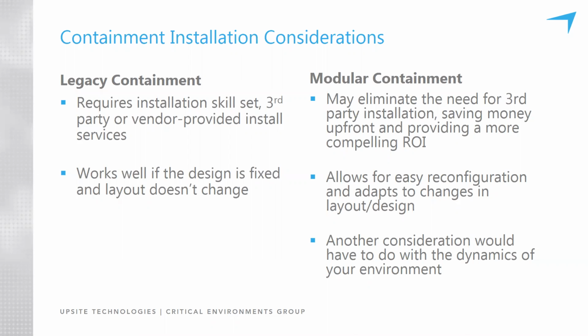My last point here would be that there's specialty situations that exist. We run into them seemingly more times now than not. Don't know the reason for that, but examples would be like a row that ends with a UPS or an RPP. So people might deploy power to all the cabinets on either side of the aisle through a row-ending UPS and RPP setup. So if you've got that kind of situation, this might not be conducive to modular or mechanical attachments due to the size and or equipment warranty issues. So there's absolutely ways we can accommodate these situations and are mostly treated as a one-off, and those almost always require some sort of site scoping visit and consultation with the end user or owner.